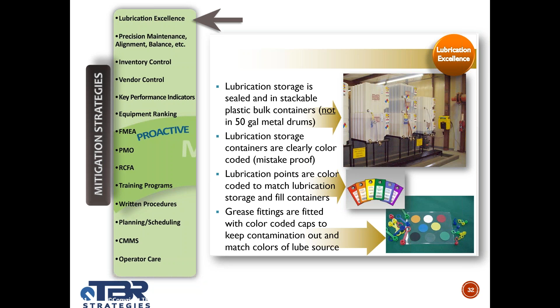Another key thing is grease guns. If you have more than one grease, which you usually need, you can't use an EP additive on motors because it'll attack the windings in the motor. So you don't use a grease with an EP in a motor, so you don't want to mix that up with the ones you use in bearings. So you want to color code your grease guns, and you want to analyze this for proper service and make sure that we know the proper amount to apply. It's not that one grease is good, two is better, and 50 is outstanding. We need to understand the proper amount of grease.